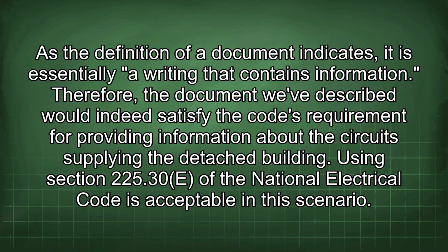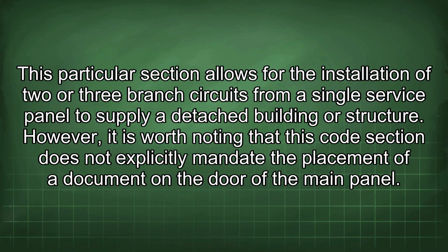Using Section 225.30(E) of the National Electrical Code is acceptable in this scenario. This particular section allows for the installation of 2 or 3 branch circuits from a single service panel to supply a detached building or structure. However, it is worth noting that this code section does not explicitly mandate the placement of a document on the door of the main panel.